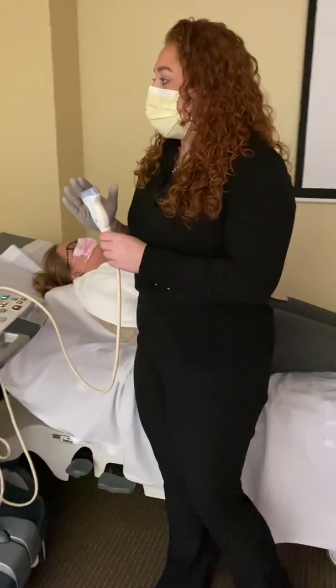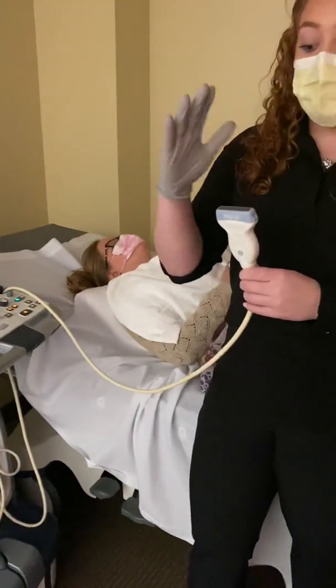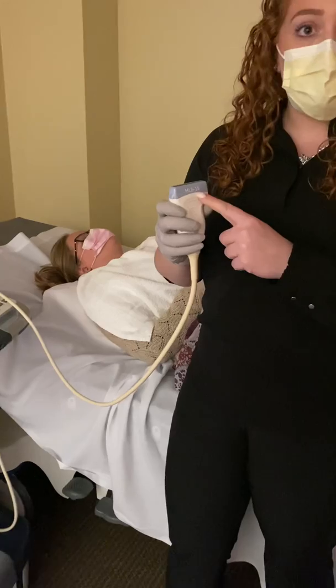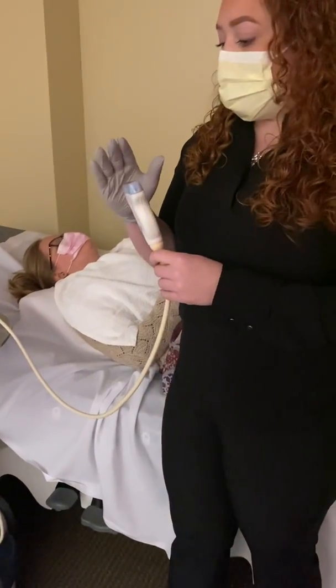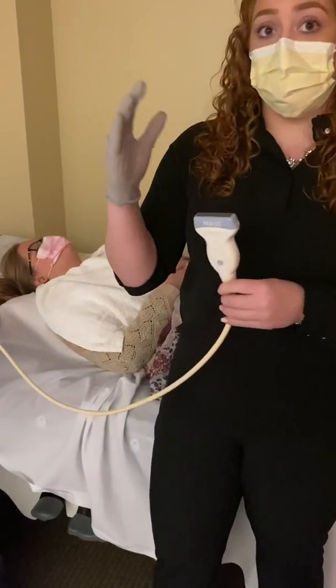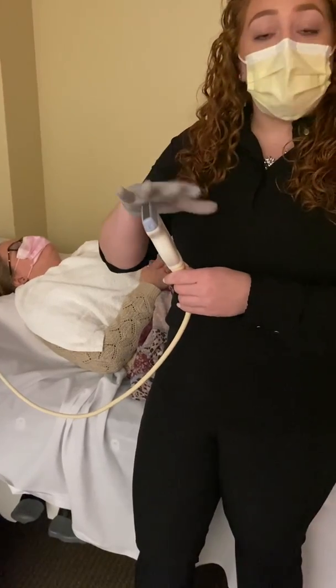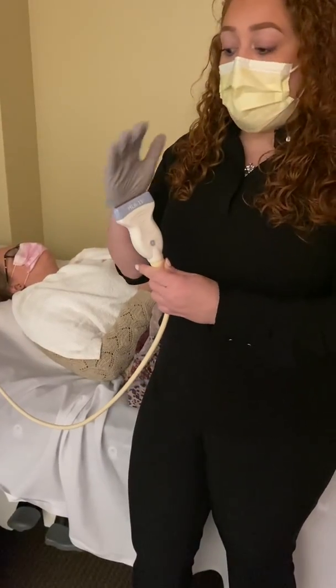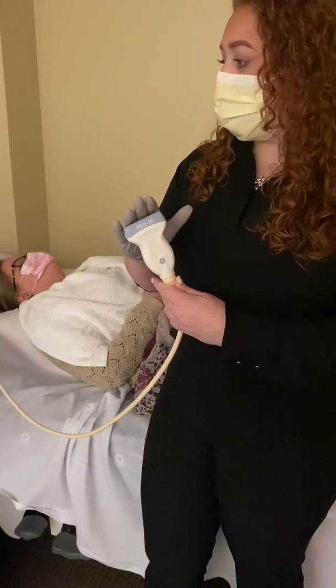So when we're doing anything that's superficial, we want to use our linear probe. So this is the 15 megahertz probe. This is going to be scanning anything that is very superficial. So the higher the frequency, the more superficial the area that we're going to be scanning. So we're going to be using this probe here.